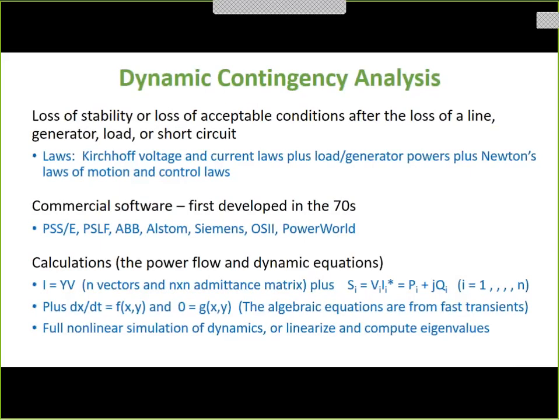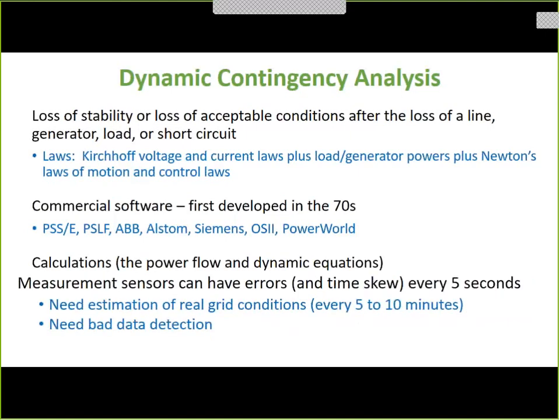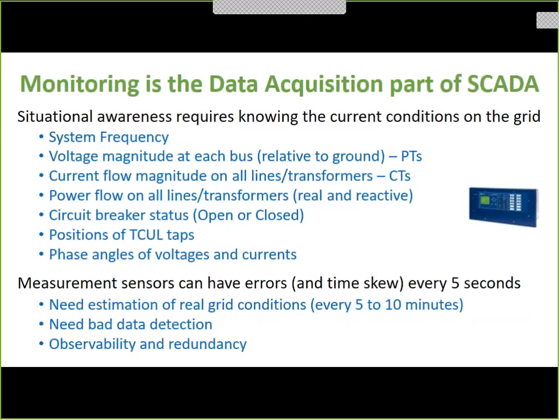Okay. Now, dynamics. Loss of stability is what might happen as a result of this. That means that generators lose synchronism with each other and they start to slip poles, and that's a big no-no in our business. So they will trip on a loss of out-of-step relay. Same commercial software. The calculations are the same. You still need all of these steady-state equations, but you have to add to them all the dynamic equations associated with the generators and their control systems. So you need to do numerical simulation. It's hard to use Lyapunov stuff. People have tried for years, but the industry keeps going back to numerical integration. Just integrate the dynamics and see what happens.